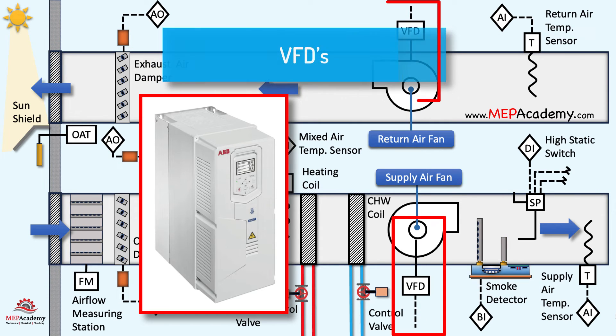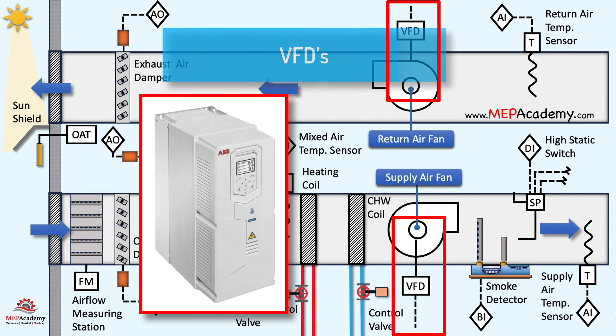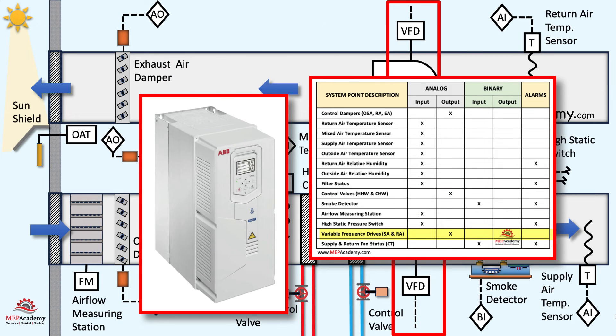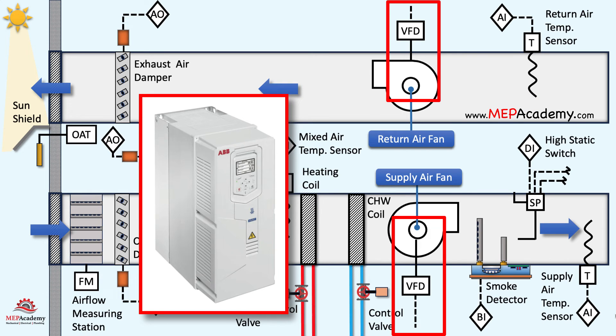One of the primary functions of a VFD on the supply and return fans is to enhance energy efficiency. The VFD allows the speed of the fan motor to be adjusted based on the actual demand for airflow. This prevents the fan from running at full speed constantly, which can result in energy savings especially during periods of partial load. VFDs enable soft starts and stops for the supply fan motor, reducing mechanical stress on the motor and associated components, extending the lifespan of the equipment. The gradual acceleration and deceleration also contribute to smoother operation.